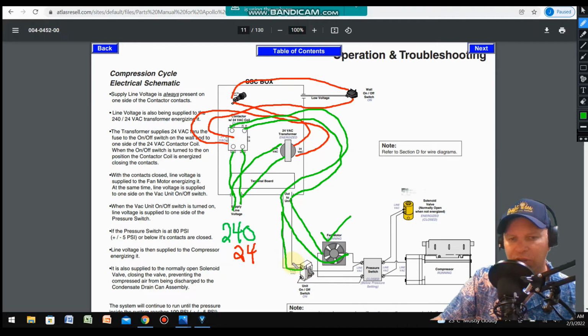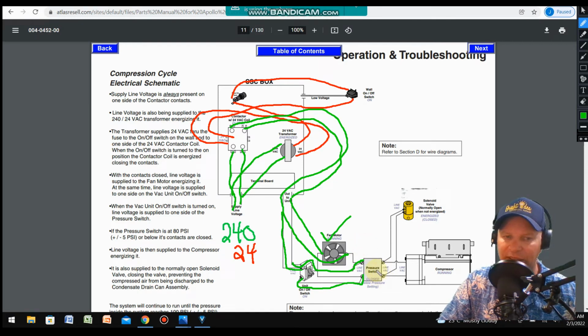Okay, so we'll kind of go like there. Okay. Now, when the vac unit on-off switch is turned on, the line voltage is supplied to one side of the pressure switch. And so if that's on, you basically have that voltage going there to a pressure switch. Now, what the pressure switch does is if the pressure is less than 80 psi or 85 psi, it will go ahead and close.